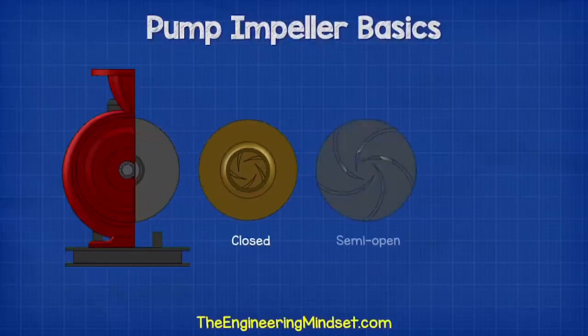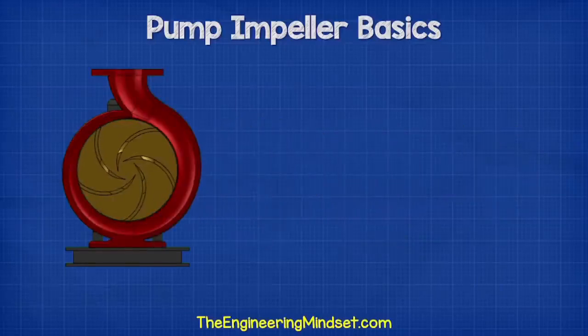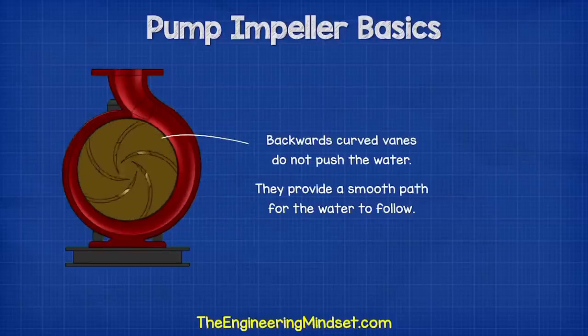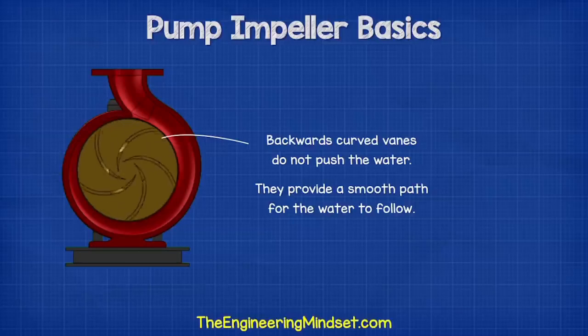There are many types of impeller, but most will have these backward curved vanes which will either be open, semi-open, or closed with some shrouds. These backward curved vanes do not push the water. The curves rotate with the outer edge moving in the direction of the expanding volute. These vanes will provide the fluid with a smooth path for the water to flow, as we'll see a little later in this video.